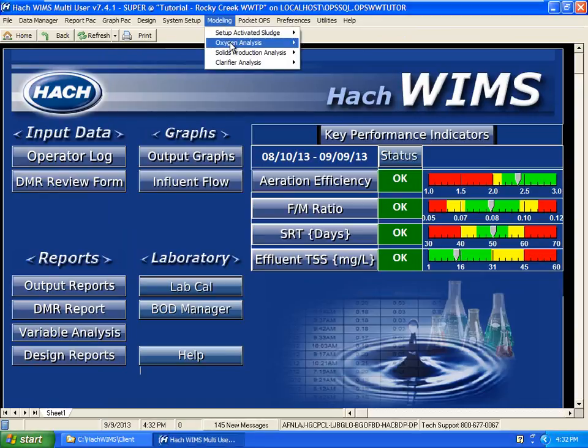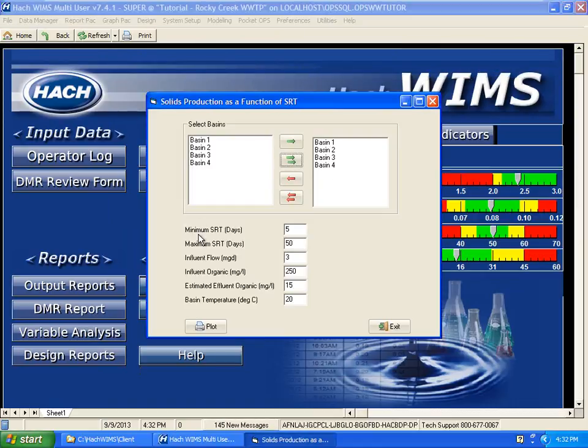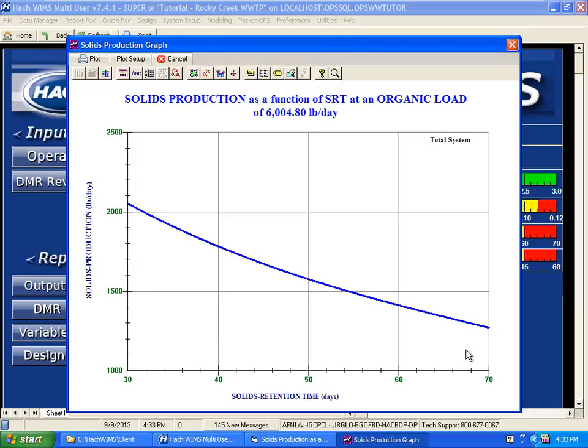I can do the same graph but instead of changing the mixed liquor, I'm going to do it based on SRT. Looking at all four basins, what if I change my SRT and vary it from 30 days to 60 days? My Influent Organic is going to average about 250, my estimated effluent organic is 15, and the basin temperature is 20°C. I plot this, and given these solids retention times, I'm able to predict what my solids production is going to be given certain organic loads. I can run this graph over and over, print out certain organic loads, and put them on the wall for reference. Combined with the oxygen analysis done earlier, we can tell what kind of solids we're producing and play what-if games with our SRT or mixed liquor suspended solids.